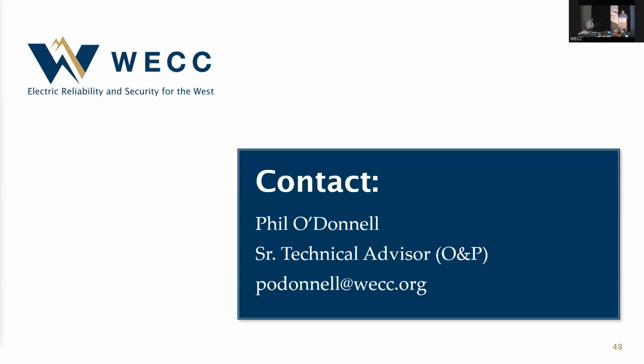Great. The next question, I've got a little perspective on it, but it's asking when WECC adopted the definition of a facility extending through the breaker, and has this always been the case? I would say there may be instances where we might not have asked for evidence of things, but we're not creating a definition or a requirement or modifying the requirement. We reserve the right to get smarter in terms of the information that we ask for. I would parallel that with the approach across the enterprise over the last couple of years to begin to do walk-down confirmation of facility ratings, because in the past we tended to rely on evidence that was presented, and then in some instances we started to walk down and discovered that operationally there was a distinct difference. So there too the obligation under the requirements hasn't changed, but over time, as we've evolved our approach, we look at it a different way.